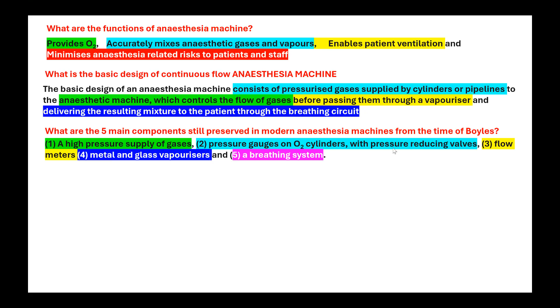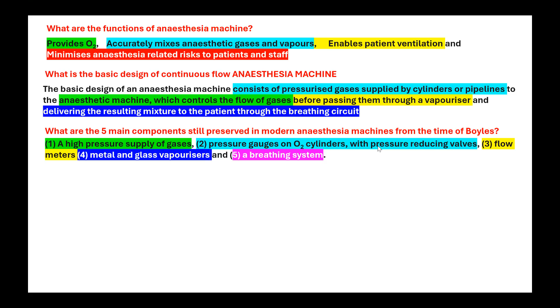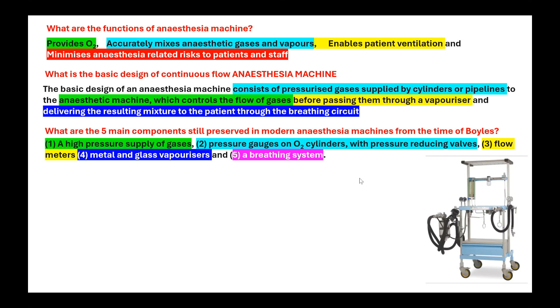That is because the gases are supplied at a very high pressure and they cannot be directly delivered to the lung. What will happen if you supply gases at 2000 psi? Barotrauma. You will rupture the alveoli. So it is very highly dangerous. So we have to reduce it to safe limits. That is done by the pressure reducing valve. So from the earlier question, one more thing you have to remember is all the machines require a pressure reducing valve and also a gauge to show what is the pressure that is being there in the machine. Okay. So this is the basic model.